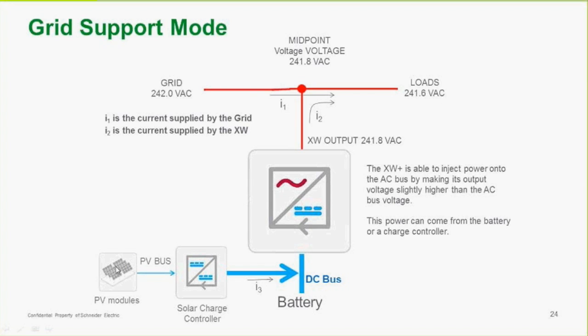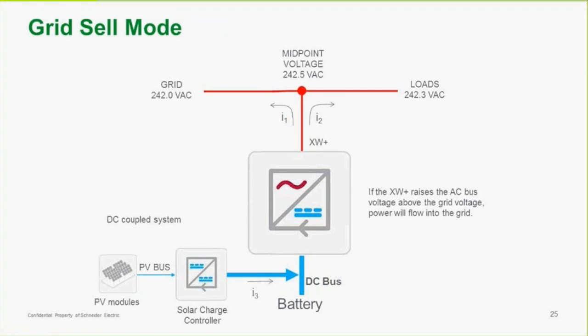So this power can come from the battery. This power could also come from the PV bus. And you'll note here that we have a solar charge controller and an array, so this is actually a DC coupled arrangement, and we'll talk about that more later. In grid sell mode, we can sell power back to the grid for a FIT program, and so if the batteries are charged up and there's excess power, it can be supplied to the grid. It can also be supplied to the loads. So it's basically assisting in powering the loads or selling back to the grid.